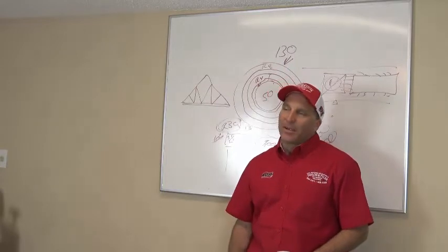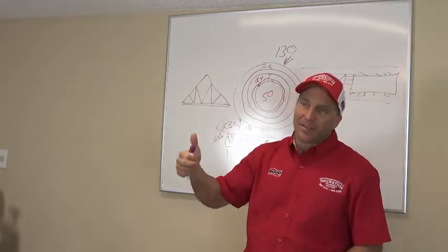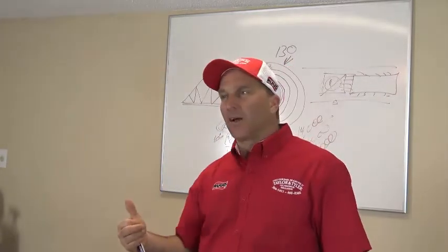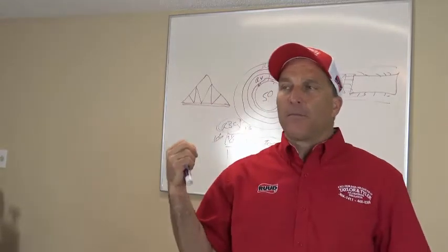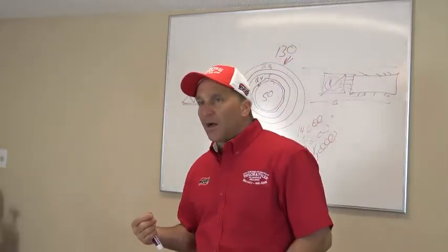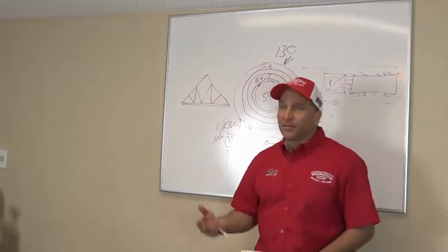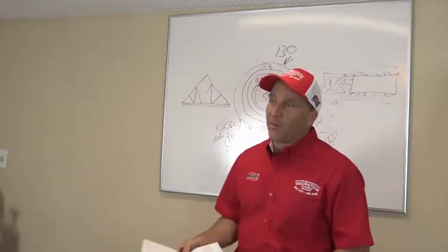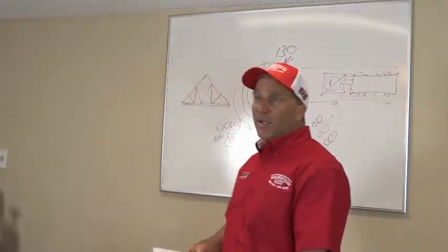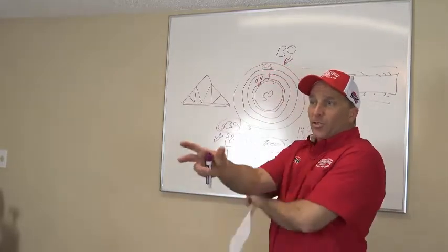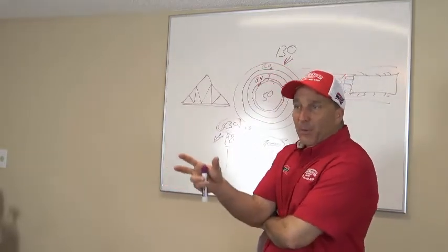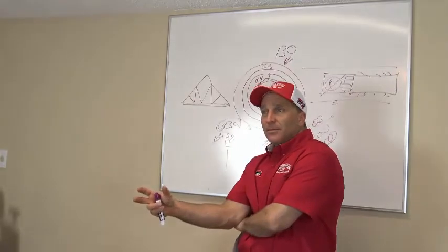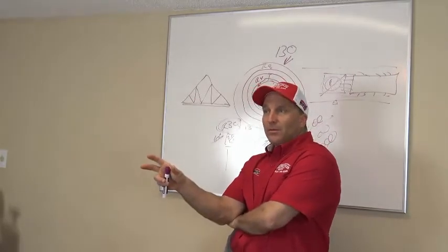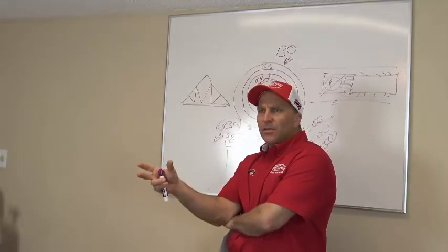What do I mean by indoor air quality? Humidity level inside the house, temperature inside the house, mold mildew spores, dirty molded supply plenum that we just found. Are you going to tell me you got good indoor air quality when I just took a picture of your plenum and showed you all the mold? Can I put good on there now? No. Don't I have to put poor? Well, why are you putting poor on there? You see, you checked off poor.